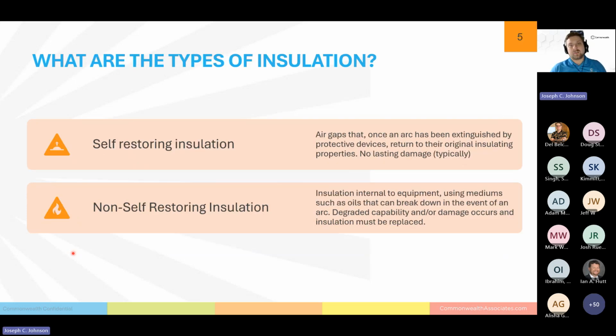So just starting off, what are the types of insulation? There are 2 types of insulation. One is called self-restoring insulation. This is air gaps that are outside of the equipment, right? Those stacks of insulators you see on all of the substations, that's really an air gap there. And when you have an arc, that's ionized the air, and the air is effectively becoming a path for electricity. It's significantly lower than a normal breakdown of air. And when that arc is extinguished by whatever means, the breaker opens, your protective devices interrupt that, the new air rushes in and replaces the old air, the ionization goes away, and that insulation returns to its former glory. It's now just as good as it was before. Typically no damage, unless maybe your protection didn't interrupt fast enough, but no real damage here.